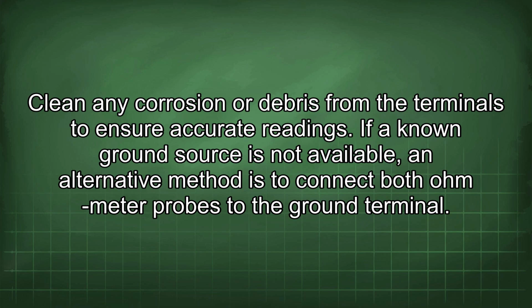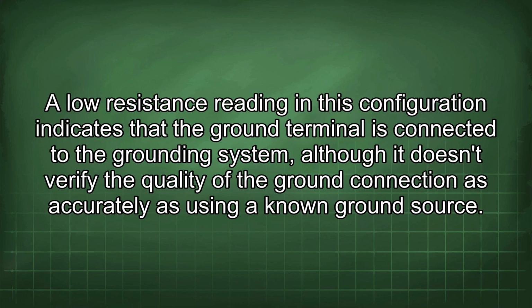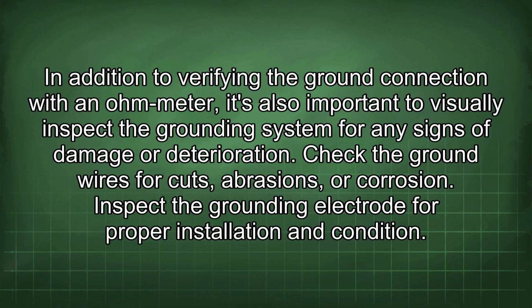If a known ground source is not available, an alternative method is to connect both Ohm-Meter probes to the ground terminal. A low resistance reading in this configuration indicates that the ground terminal is connected to the grounding system, although it doesn't verify the quality of the ground connection as accurately as using a known ground source. In addition to verifying the ground connection with an ohm-meter, it's also important to visually inspect the grounding system for any signs of damage or deterioration.